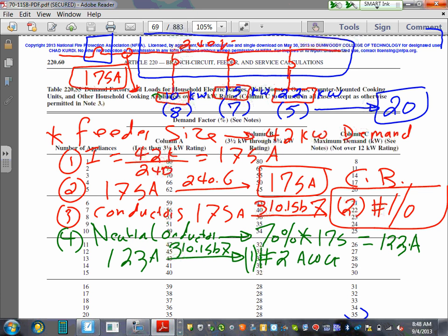So the 70% size of your neutral, because the neutral that's going to all these ranges is carrying the unbalanced current between hot 1 and hot 2, and from knowing how the load acts, it's not going to be carrying a full load. So they allow you to chop it from the get-go by 70%. Now, where did I get the 70% from? 220.61. Section 220.61, guys, tells you for ranges and dryers, you derate the neutral 70%. Okay, so have I said that?